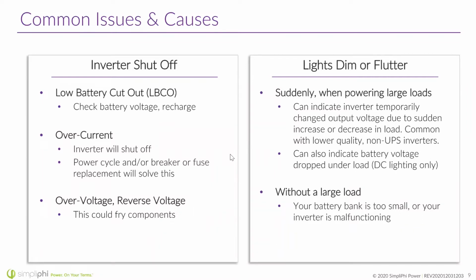So if you're having a low battery cutout event, make sure to check your battery voltage and then recharge your battery. If your inverter has turned off, it could simply mean that your batteries are drained and your inverter has disconnected from the batteries to protect them. Your inverter could also be shut off because of an overcurrent event. Maybe you've drawn too much power and you simply need to turn the inverter off and then back on, or maybe there's a breaker that you need to flip back on.